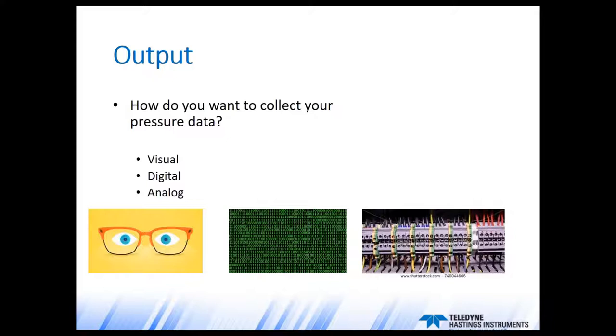How are we going to look at the output of the vacuum gauge? It really comes down to three areas: visual, where you simply look at the gauge and know the pressure; digital output, where the digital signal is connected to a central control module like a PC; and analog, where a proportional signal — either voltage or current — is connected to a PLC or DAC card. For many gauges, you don't have to select just one — there are advanced digital vacuum gauges that may offer all three: a display as well as analog and digital outputs.